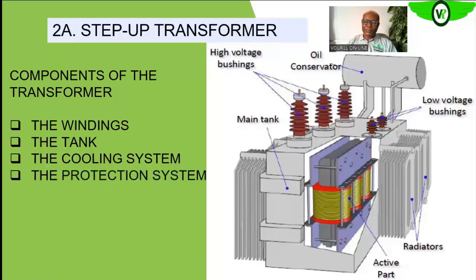So we also have other protective systems that protect the transformer against excessive temperature. We know the effect of excessive temperature as we stated earlier. Because of that I squared R effect, as you are loading the transformer, the heat will build up to a stage where it can cause the breakdown of the winding insulation. And once that happens, it can cause a turn-to-turn short or a short to ground, as the case may be. All of those are undesirable circumstances that we do not want in our transformer.